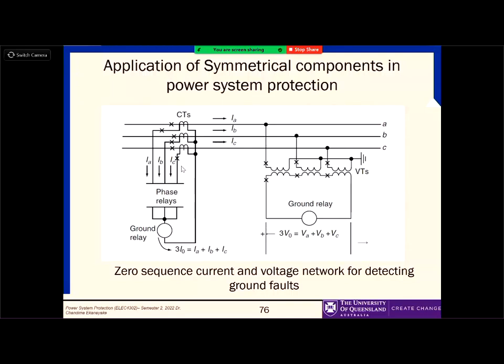If you connect one of these transformers with the reverse terminals, then you will be in trouble. You won't see what you want to see on this side, because there is a 180 degree phase shift. So remember, when you go into the industry, you will find, based on the standards, how to represent the connection sides, where the dot is.